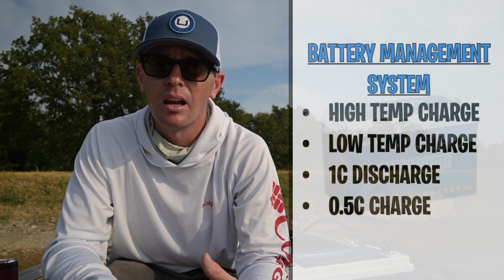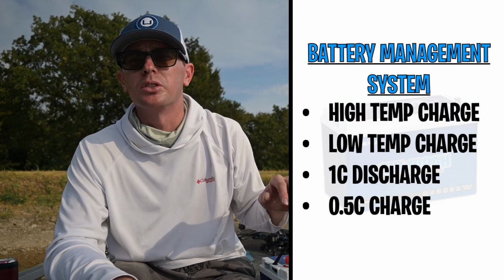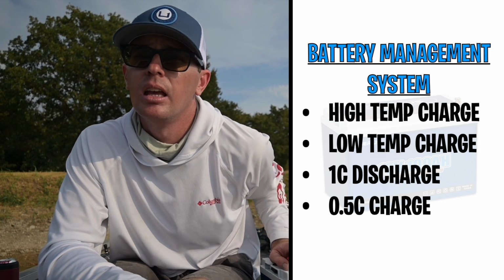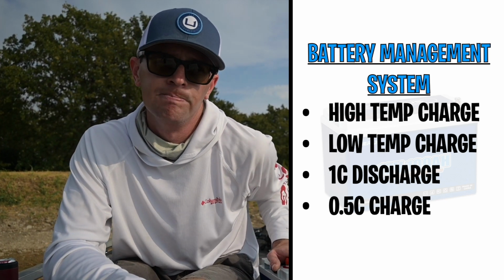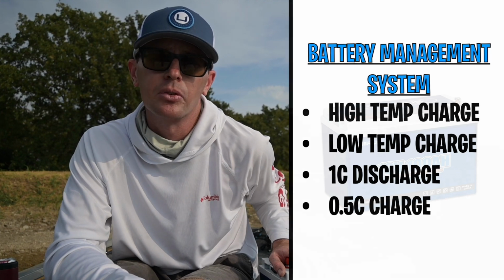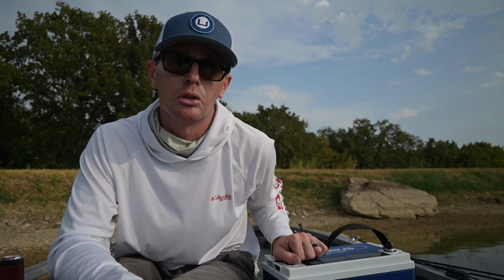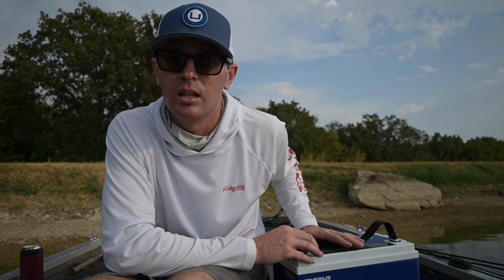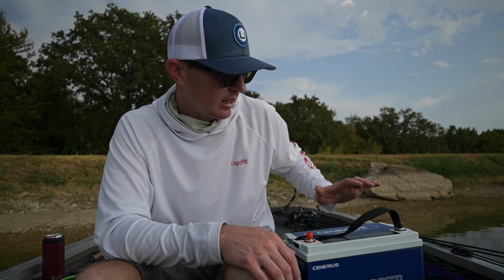BMS, or the battery management system, is something that always comes up when you're comparing batteries. There's a handful of different features and functions you want to keep your eye out for. This has all the basics: low voltage cutout, high voltage cutout, short circuit, high temp cutout, but it also has low temperature cutoff, which is something you want to pay attention to if the battery is going to be charged below freezing. If you live in Florida, this is probably not a problem for you. This would be a problem if you're ice fishing or up in the north. You can discharge it while it's freezing, that's cool, but charging it is where you run into a problem, and it does have low temperature cutoff, so you won't have any lithium plating problems - it'll basically save itself, and when the battery warms up, it will charge.